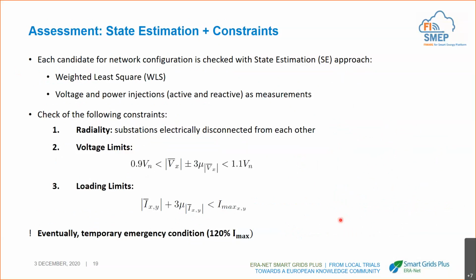So for each candidate, once we forecast how the situation will be in case we apply it, we have to verify 3 constraints. The first one is the radiality, as I said at the beginning, so that the feeders are electrically disconnected from each other. The second is the voltage limit. And the third is the loading limit, so the amount of current that is flowing in each line. In case these constraints cannot be respected, we can accept a temporary emergency condition for a limited period of time.